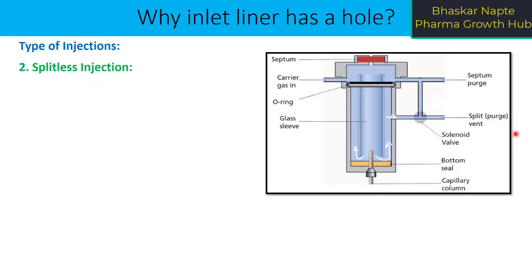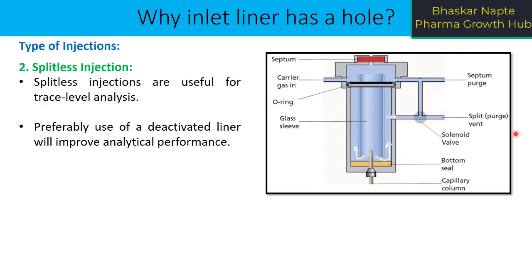The second type is splitless injection. Splitless injection is generally used for trace level analysis where sample concentration is low. Preferably, use of a deactivated liner will improve analytical performance. In splitless injection, your sample is going to get in contact with the bottom seal, as you can see in the diagram. Once the splitless injection gets completed, the split vent opens up and whatever solvent vapors are present in the liner get vented out through the split vent.